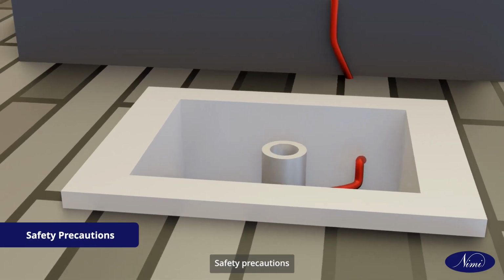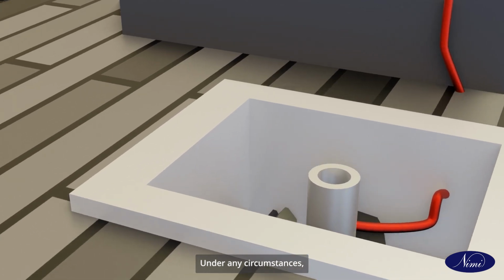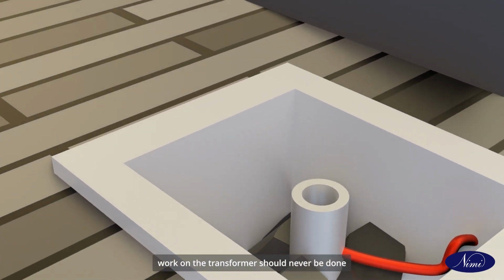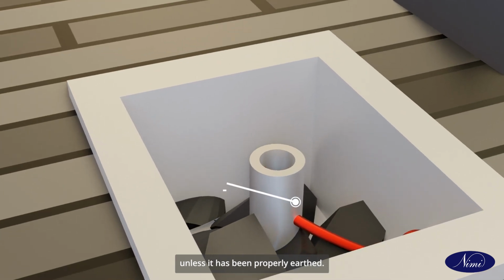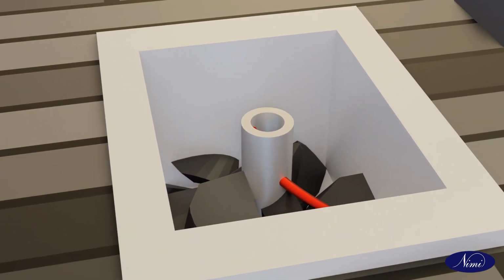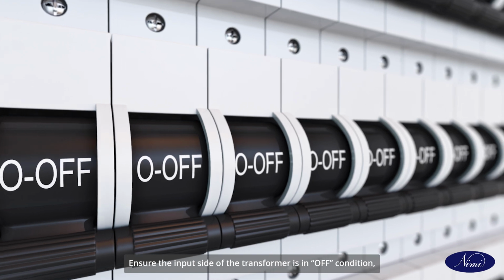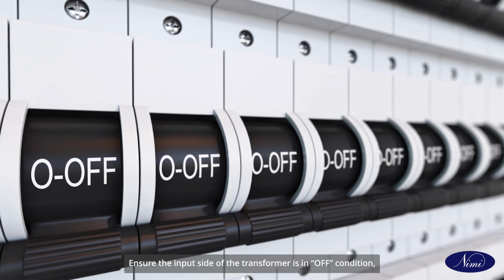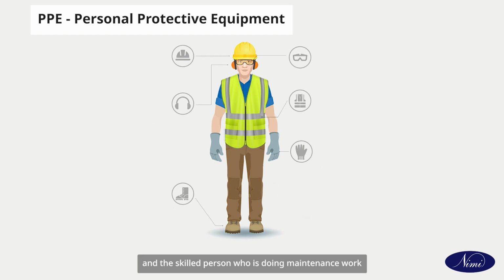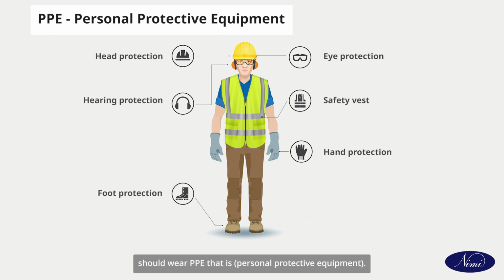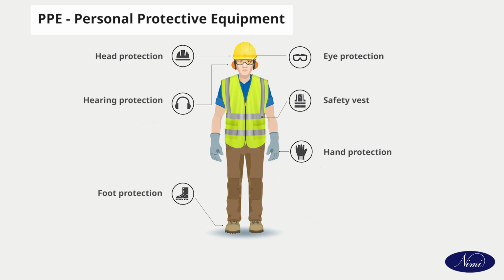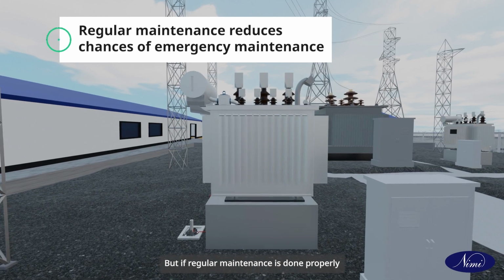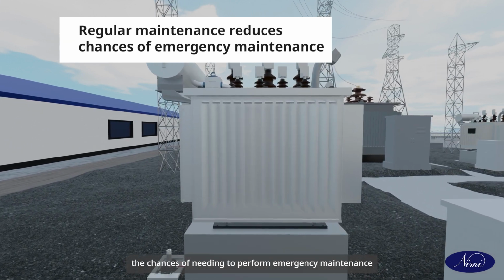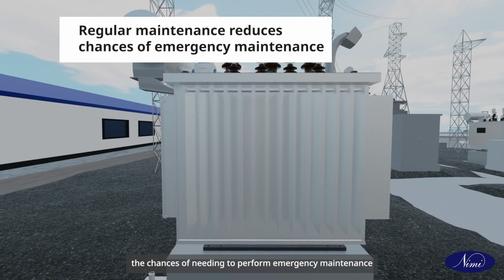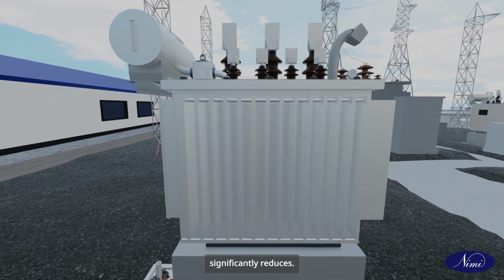Safety precautions. Under any circumstances, work on the transformer should never be done unless it has been properly earthed. Ensure the input side of the transformer is in off condition, and the skilled person who is doing maintenance work should wear PPE, that is personal protective equipment. But if regular maintenance is done properly, the chances of needing to perform emergency maintenance significantly reduce.